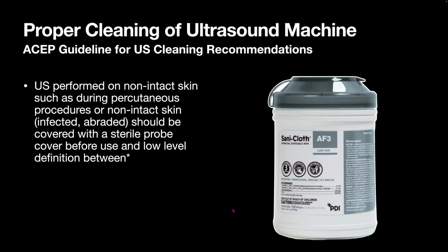Now, if you're, say, performing an examination on intact skin and it comes into contact with a patient's bodily fluids, you want to clean it with these gray AF3 wipes and consider sending it to the department that you have a previous agreement with to have high-level disinfection performed. Again, high-level disinfection isn't necessarily always needed, but for our purposes, I highly recommend it if you're performing an ultrasound and it comes into contact with blood or bodily fluids. There are some wipes that are considered high-level disinfection, but we do not have them at our institution at this time.